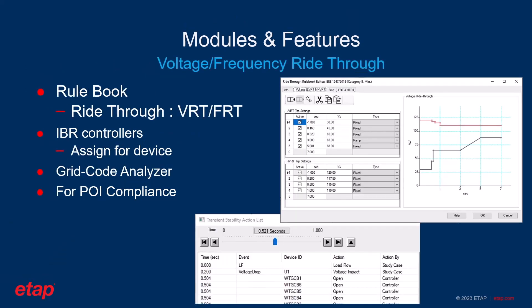Similarly, for ride-through studies, the user has the capability to go through the rulebook and define the ride-through capability of their assets in terms of voltage ride-through and frequency ride-through. They can also assign their primary control to elements. ETAP provides its own primary controllers for PV, WTG, and inverters, which can be easily hooked up with the grid code analyzer for conducting final ride-through studies at the point of interconnection.